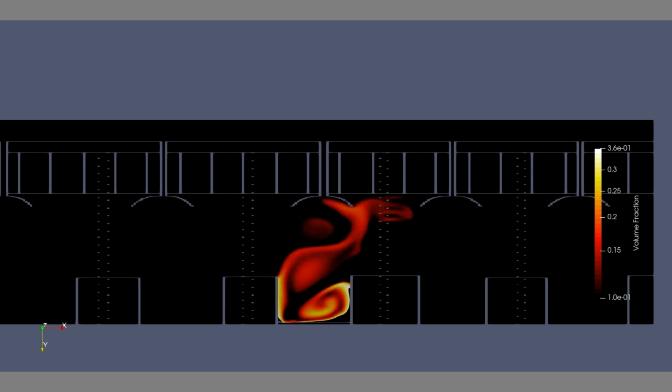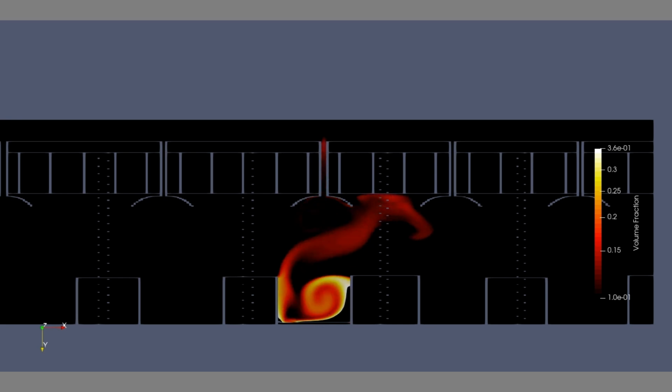And you can see that initially the cloud is small, but it's growing over time. The cloud builds up near the ceiling of the laboratory. So you can see a fairly large flammable cloud extending from just above the spill, just above the surface of the liquid, to the ceiling, spanning the distance of these 3 suction vents.